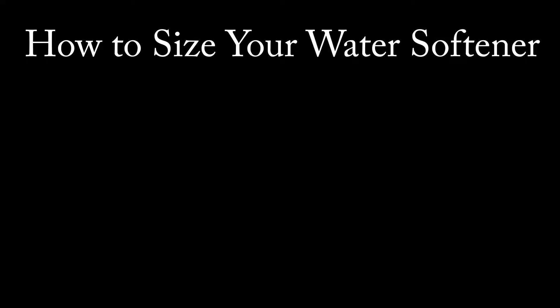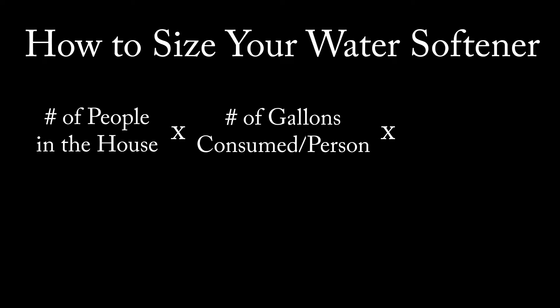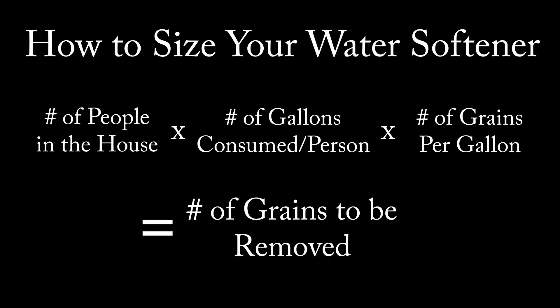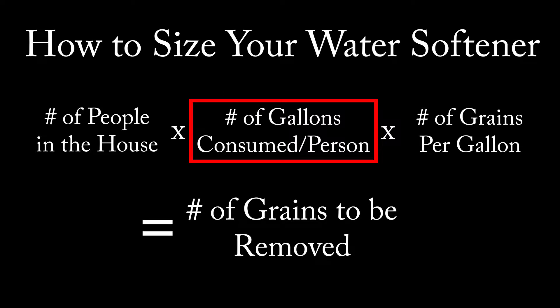This is the formula to properly size your water softener. It's the number of people in the house times the number of gallons of water consumption per person times grains per gallon, and this will equal the number of grains to be removed.